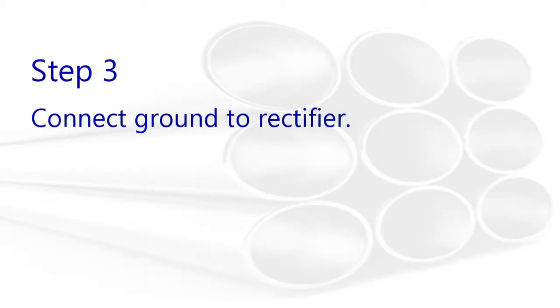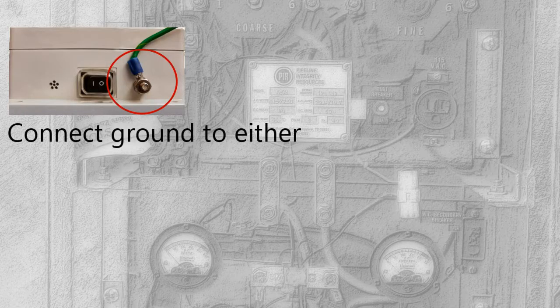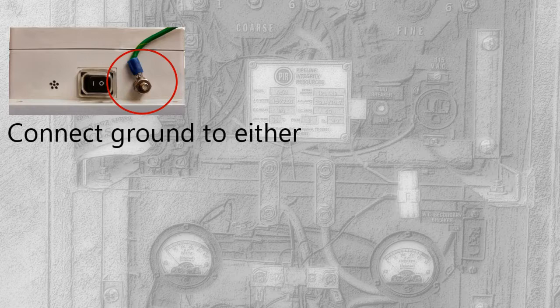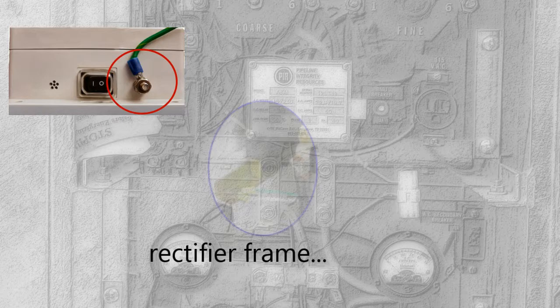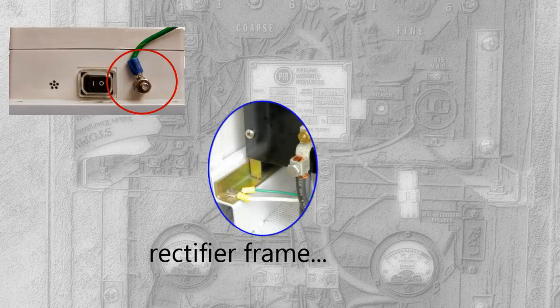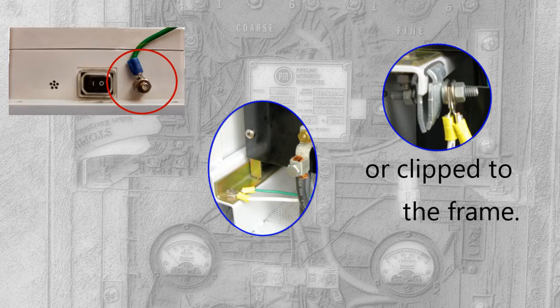The RM4150 and RM4151 are shipped with a ground wire already attached to the unit. Ground the unit by connecting the ground wire to the rectifier ground. If necessary, you can use a clamp to attach the wire to a paint-free portion of the rectifier frame.